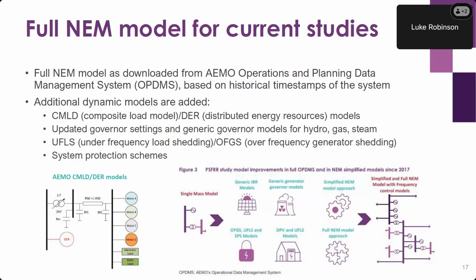In addition to this, for the risk review studies, we add in additional dynamic models to improve the accuracy of our simulations. We'll add in composite load and distributed energy resource models to more accurately represent load and DPV shakeoff and the response to faults. We'll also update governor settings or use generic governor models where accurate governor models aren't available in the OPDMS system. We can also add in under frequency load shedding and over frequency generator shedding schemes if they're expected to operate for the study, and also any other system protection schemes that might be relevant to study as well.